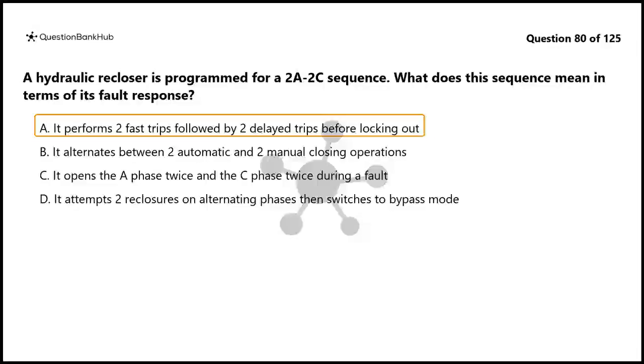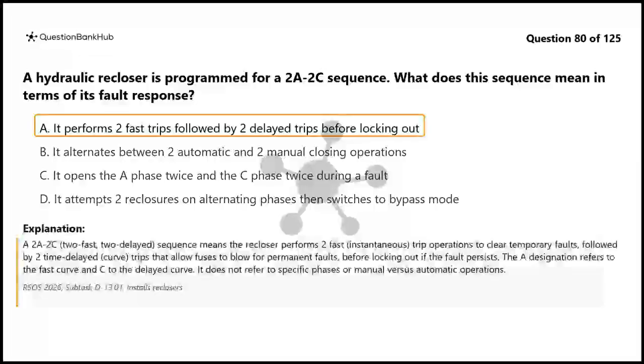The correct answer is A. A 2A, 2C, or 2 fast, 2 delayed, sequence means the recloser performs 2 fast, instantaneous trip operations to clear temporary faults, followed by 2 time-delayed, curve, trips that allow fuses to blow for permanent faults, before locking out if the fault persists. The A designation refers to the fast curve and C to the delayed curve. It does not refer to specific phases or manual versus automatic operations.